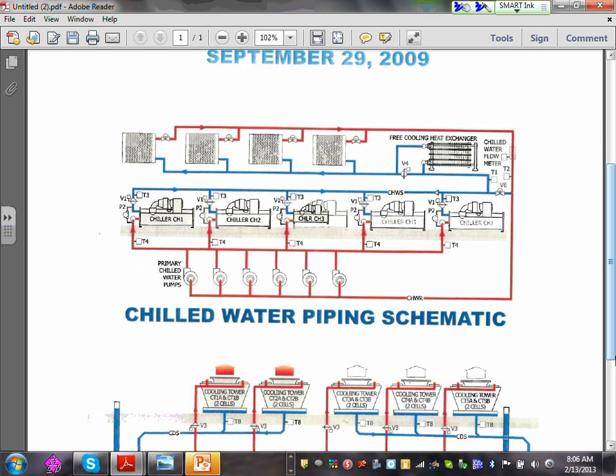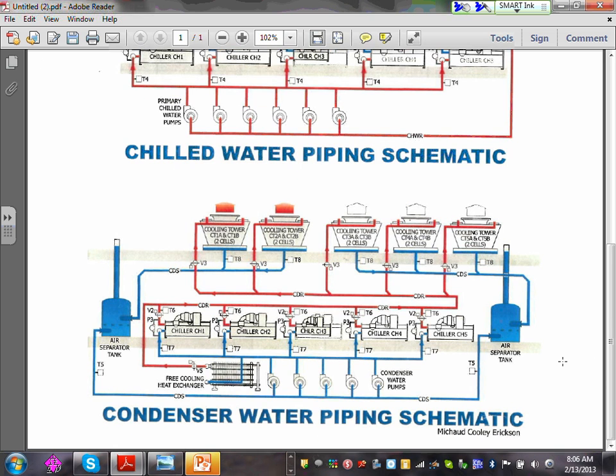This is getting deeper, guys. Remember how we said there are 2 cycles? Joe, there are 2 cycles of water. One is the outside, one is the inside. If you look at the bottom here, can you guys see, here's the chiller. They have 1, 2, 3, 4, 5 chillers to chill their building. 5 big chillers. You saw the chillers. All in parallel. They're running in parallel.